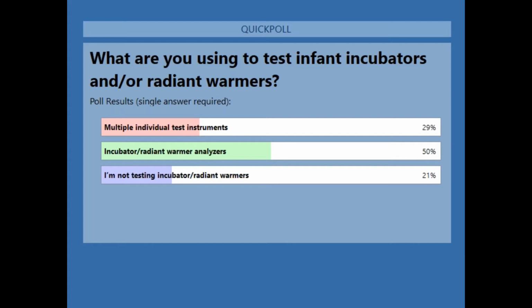And the pass data, that's good and important, but it's the failure rates you want to track, and those become your corrective action work assignments to go troubleshoot and find out what caused the failure, whatever it was. So I'm very happy to see this. Would I like to see the percentage of people actually testing with an analyzer higher? Oh yeah, I absolutely would.